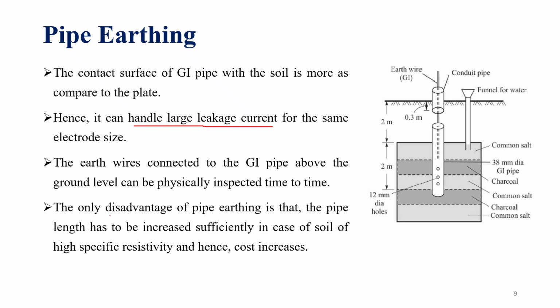The only disadvantage of pipe earthing is that the pipe length has to be increased sufficiently in case of soil of high specific resistivity. If the soil surrounding the building has high specific resistivity, then we have to increase the length of the GI pipe. So that will result in an increase in cost. Okay, that is the only disadvantage. Based upon the soil resistivity, if the specific resistivity is more, then we have to use more length of pipe. As more length of pipe is going to be buried into the earth, the cost is going to increase, and the work that we have to do in that process is going to increase. Thank you.